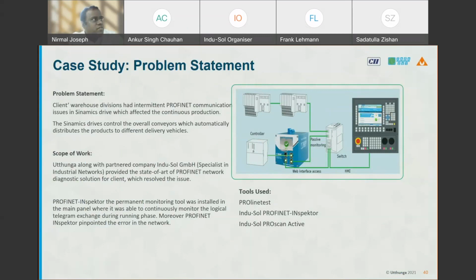I have a case study to present to you today. This is one of the sites, a warehouse division, that we visited to provide a service for resolving a PROFINET issue. Our client had Sinamics drives controlling overall conveyors, which automatically distribute products to different delivery vehicles. What they used to face were frequent, intermittent PROFINET communication issues that halted production, lost time, and caused delays in deliveries.